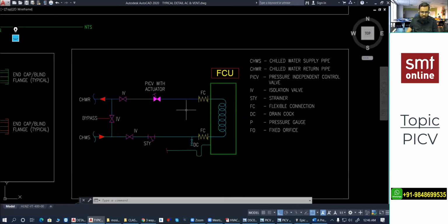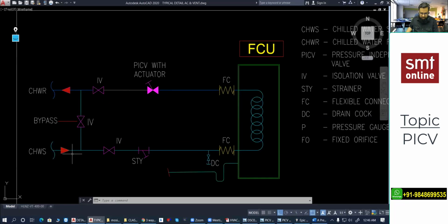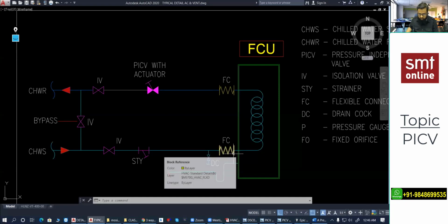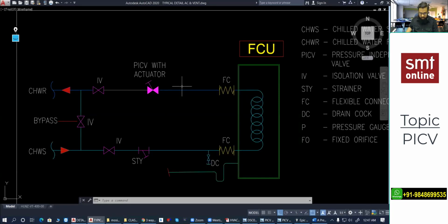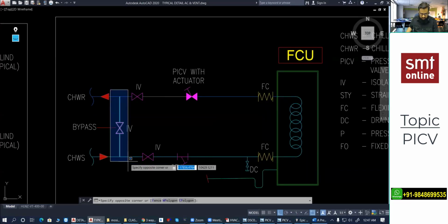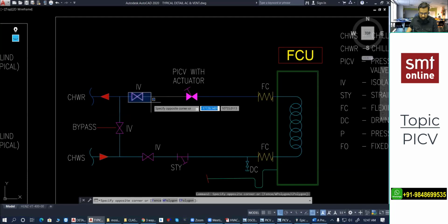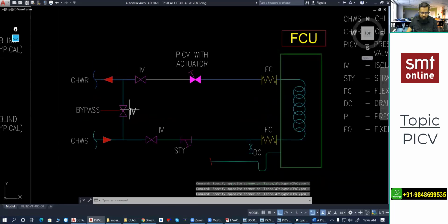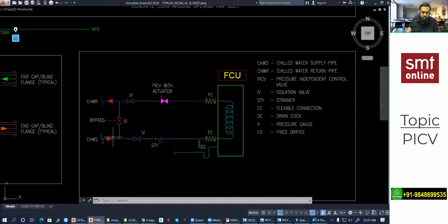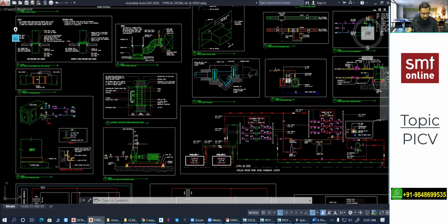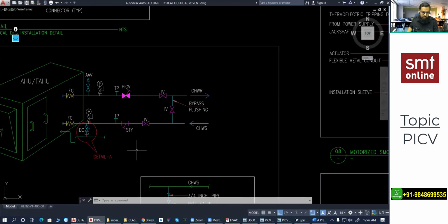This is the supply. You'll find the isolation valve, strainer, flexible connection, then the coil, then the flexible connection. Here we have the PICV, then an isolation valve, and this bypass is for maintenance. Close these two valves so that the system can be isolated, and we can open this valve so that the water can bypass. Anyhow, this is required with the two-way and three-way also. So this is the updated one, what we are dealing with in actual practice for FCU, and you'll find a similar one for AHU also. So this is about the PICV.